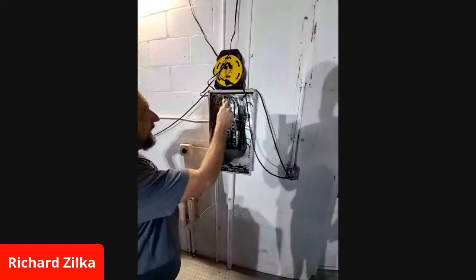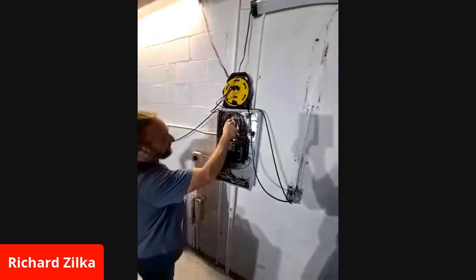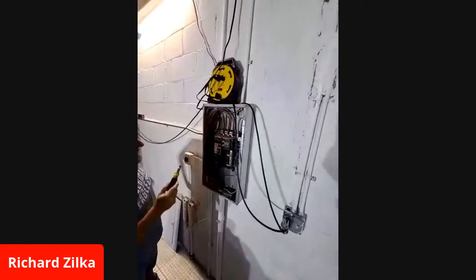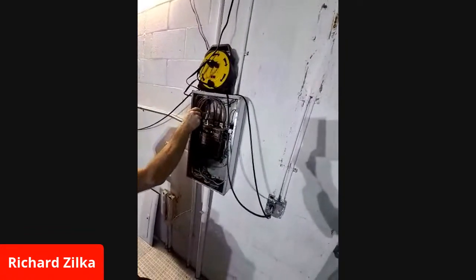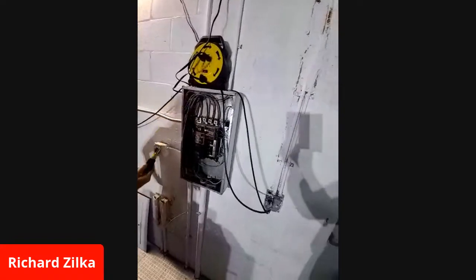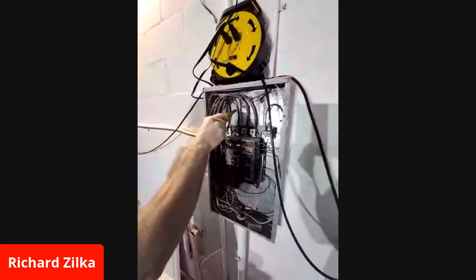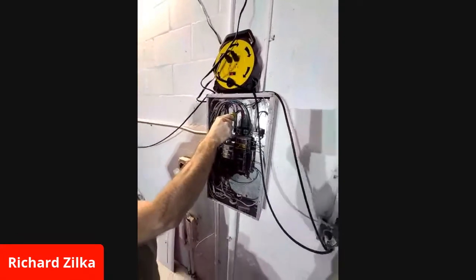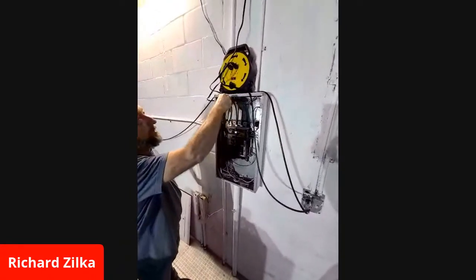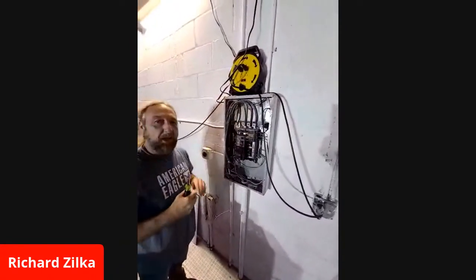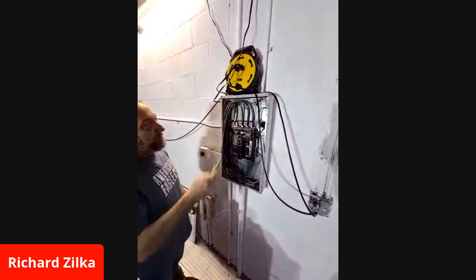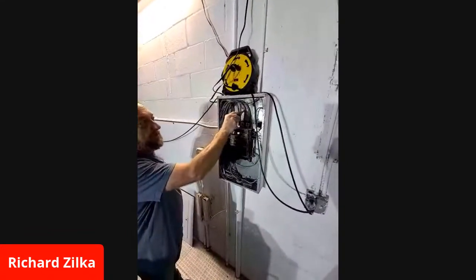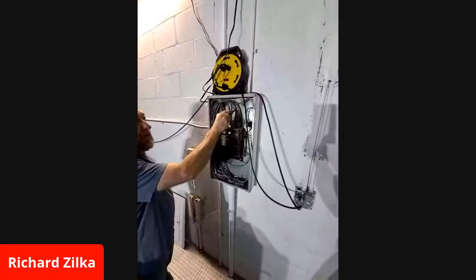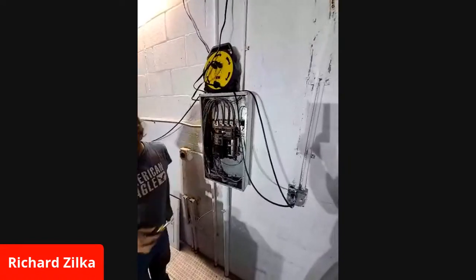Okay, so we have this, actually 3-phase: line 1, line 2, and line 3. This is our neutral, notice it's got white tape on it. How do I know it's 3-phase? This is black, they left the cable black. This is red, and if you can see right up here at the top, it's blue. So we actually have 3 lines: 240 from black to red, 240 from blue to red, and 240 from black to blue. I'll show you how to test that.